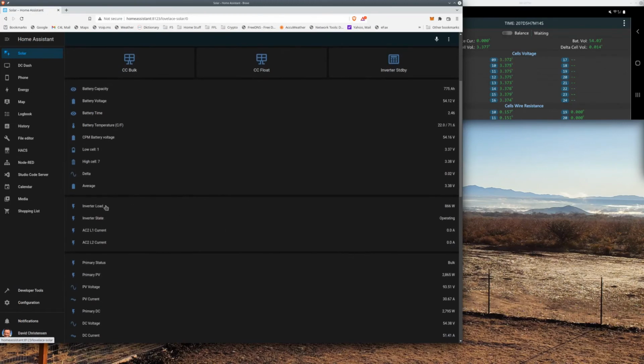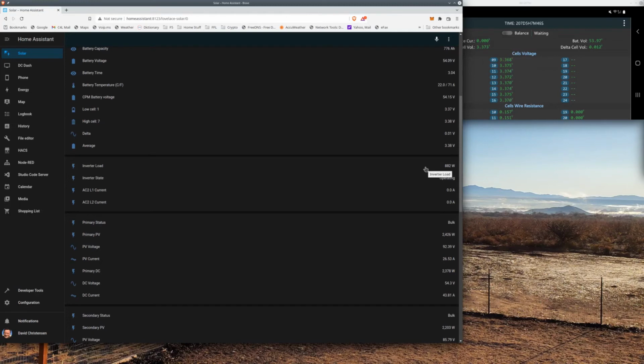Now we can go down - I think I've shown this before. I've got all the battery statistics here, the temperature. Everything from the battery temperature up is coming from Schneider. I'm connected to the Conext gateway using a program I wrote that communicates with Modbus over TCP/IP. The bottom ones here in the battery section are coming from that CPM module, and everything else down to the cells is coming from Schneider. So we've got the inverter information.